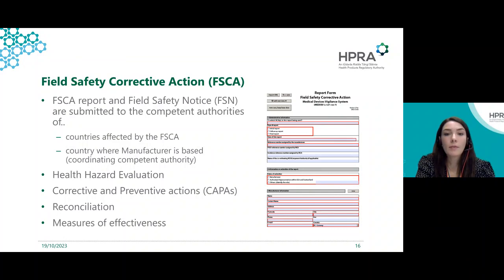For example, before it has been decided to conduct a field safety corrective action, a health hazard evaluation, which details the anticipated risk of patient or end user harm, should be performed. A corrective and preventive action, CAPA, should be triggered to investigate the root cause and corrective actions required. It also needs to be factored in how you intend to track the reconciliation and ensure that the information gets to the relevant customers. Use of a customer acknowledgement form is recommended in these cases. And finally, as Jenny mentioned in her presentation, it's important that you have a defined measure of effectiveness for your field safety corrective action and your CAPAs.